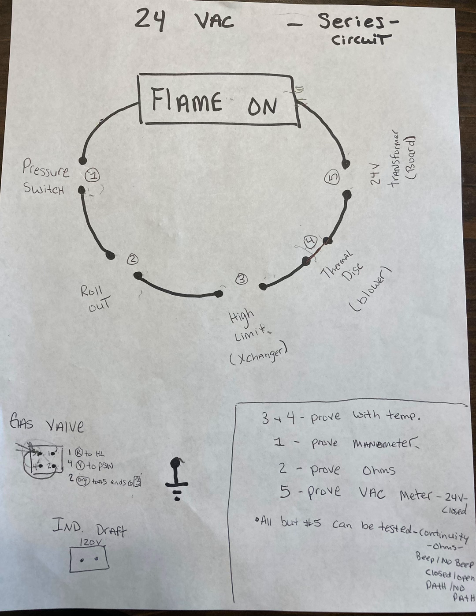We need to insert a temp probe in that area. We need to run sequence and see at what temperature did that thermal disc open, and is it indeed getting that temperature, and if so, why? Or is it a bad switch and it's lying?